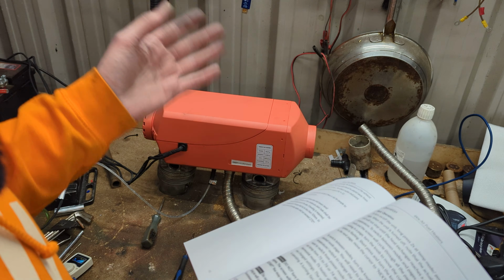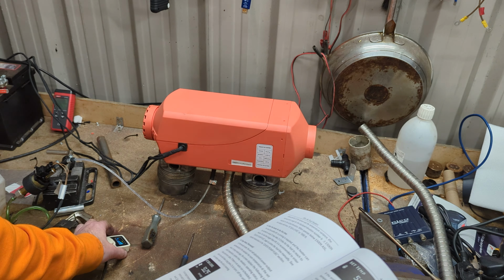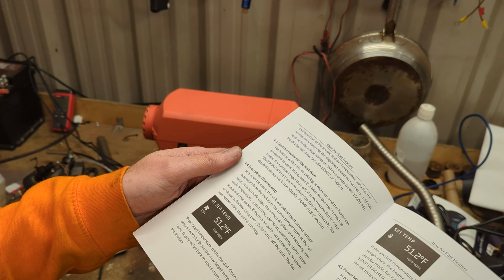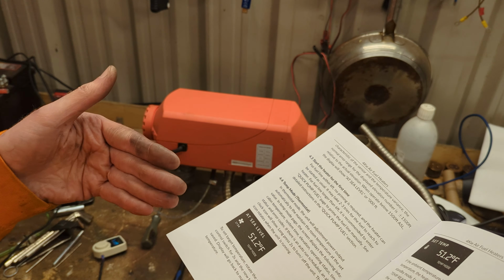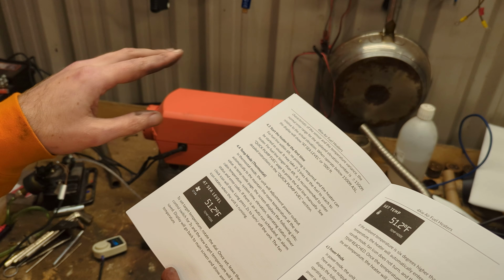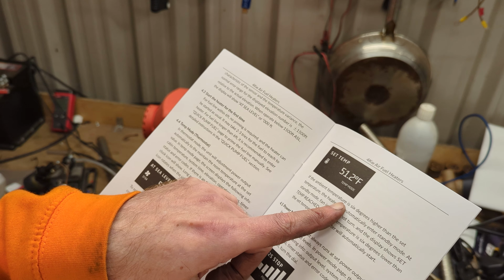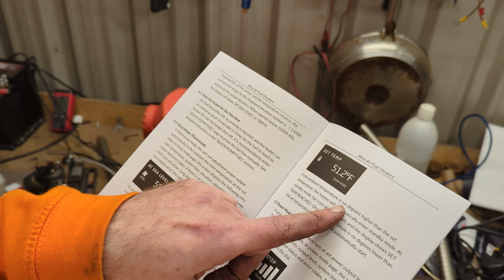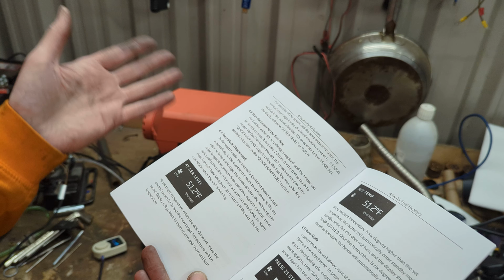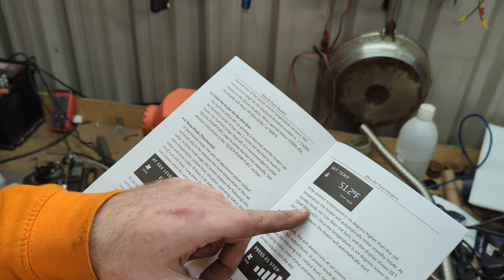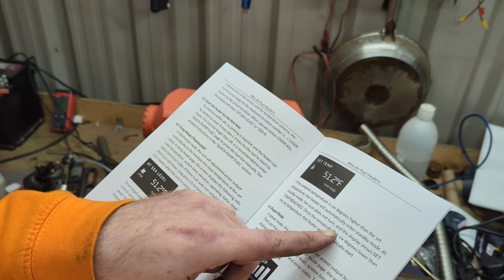Starting the heater is done by pressing and holding the big knobby dial bit for 2 seconds. There's 2 running modes: temperature mode, where you pick your temperature and it attempts to speed up and slow down to stay at that temperature. In this mode, if the ambient temperature is 6 degrees higher than the set temperature, the heater will automatically enter standby mode and turn off. In standby mode, the fan icon does not turn and the display shows set temperature reached. Once the temperature is 6 degrees lower than the set temperature, the heater will start back up again.